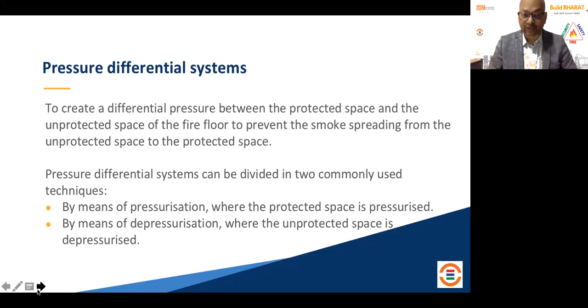So essentially, this is how it works. The area which is under fire, you are going to depressurize it, with the exhaust fan in the lobby, stairwell lobby, and here you are going to create a positive pressure in the adjoining area. So this is how you're balancing or managing your smoke. This is a supply fan which is going to create the positive pressure in the stairwell pressurization, and this is your lift.